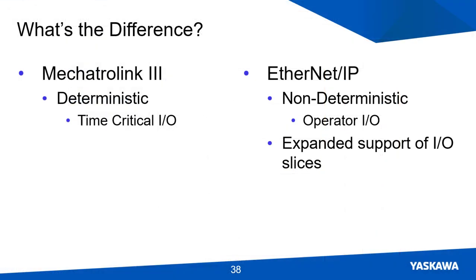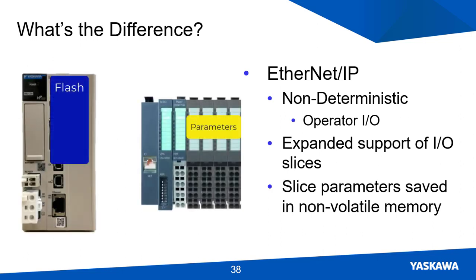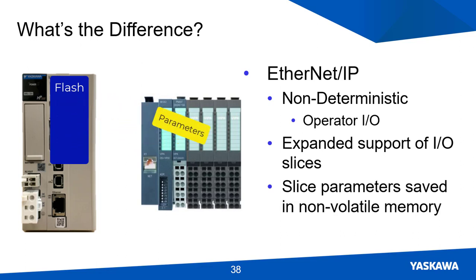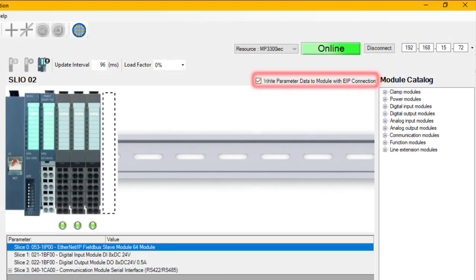One major difference when using the Mechatrolink 3 interface module versus the Ethernet IP interface module is how parameter values are stored after a reboot. When using an Ethernet IP module, the parameter settings are saved in the MPiec controller. So when the SLIO system performs a reboot, the parameter settings do not revert back to default because the controller writes the saved values upon reboot, as long as it was enabled in hardware configuration.